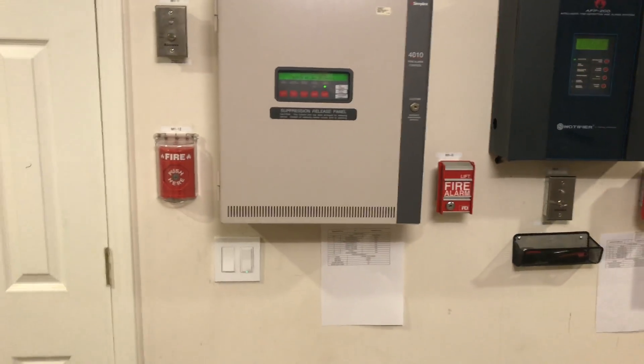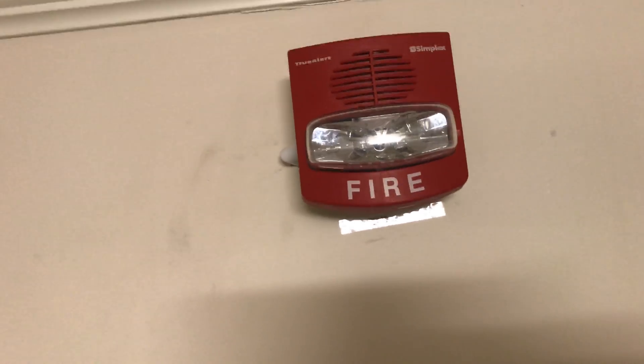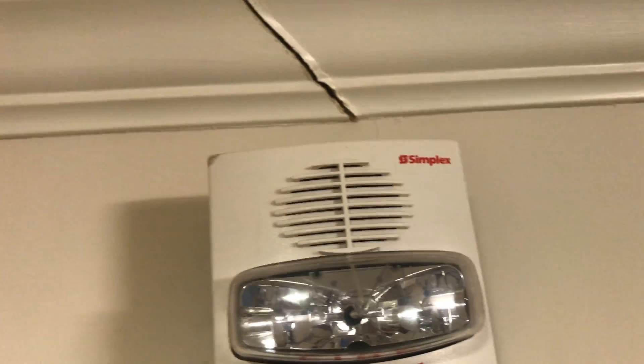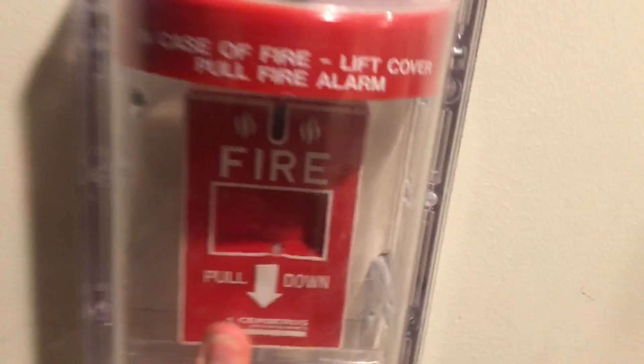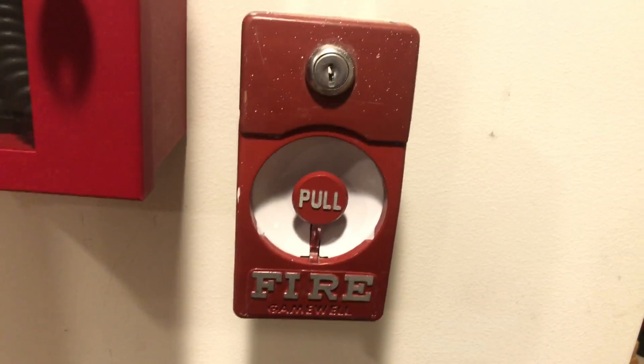If we take a step back, it's going to be a pretty Simplex type system. Going down over here is the FCI MS2 dual action lift and pull station. Going up, this is the Simplex 4903-9431 four-wire TrueAlert horn strobe, set at March time and 15 candela. Over here we have a Simplex 4903-9426 four-wire TrueAlert horn strobe, but the strobe on this is dead — it will still do March time horn, and this is fast March time. Coming down here we have the Cerberus Pyrotronics MS-151 single action pull station. And over here we have something new that not a lot of people have: a Gamewell M46-28 Century, but the key locking version.